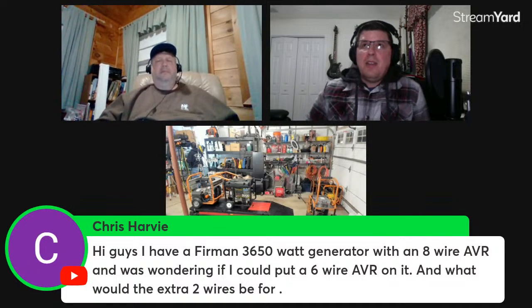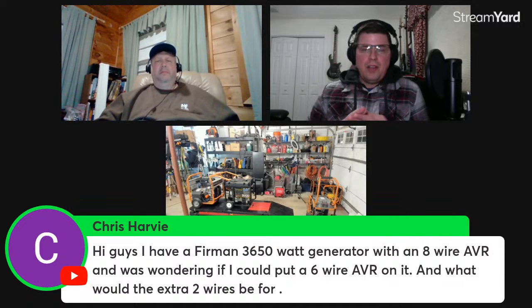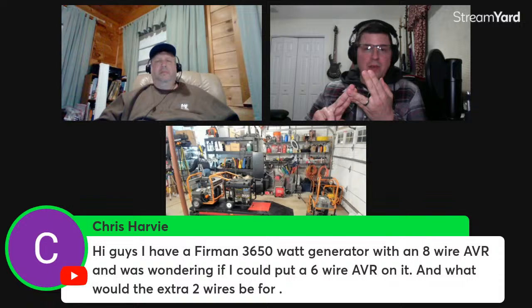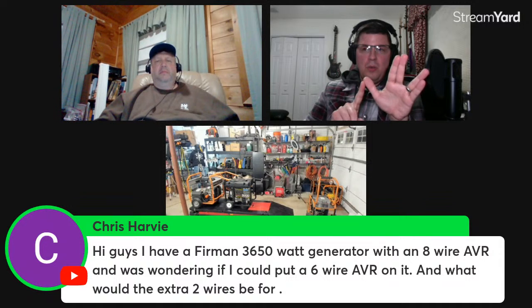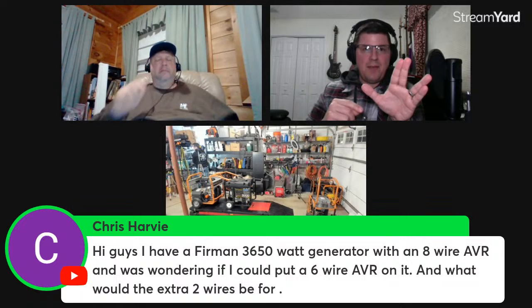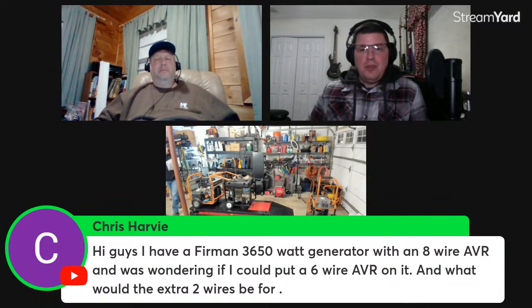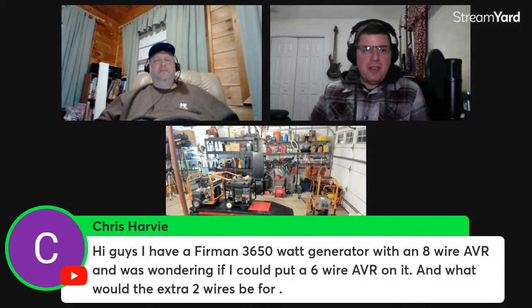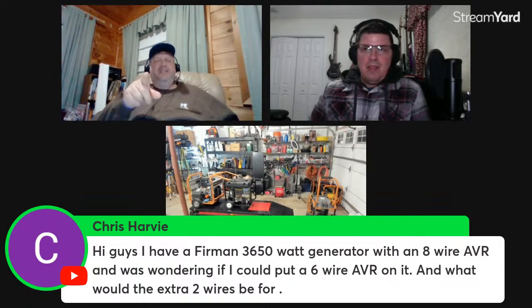On some of the Champions I've worked on, you have 2 wires that are your displaced phase excitation, or exciter windings. You have your 2 output wires for the rotor assembly, for your brush assembly. Then you'll have another 2 wires for your sensing winding—basically feeding back 120 volts, or half of the windings, back into the regulator to adjust the voltage as a feedback loop. That's 6, and then the final 2 that gives you a total of 8 is another sense.